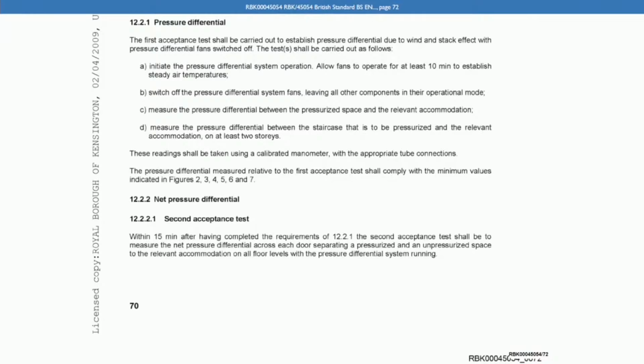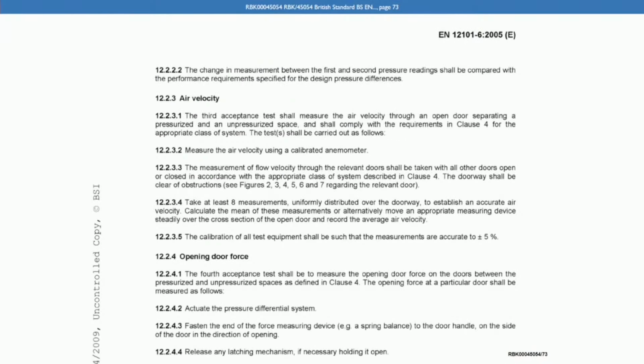And then over the page, the change in measurement between the first and second pressure readings shall be compared with the performance requirements specified for the design pressure differences. Do you see that there? I do, yeah. Now, were you familiar with that test? I have read it previously, and we did the first and second parts, but not within 15 minutes of each other.